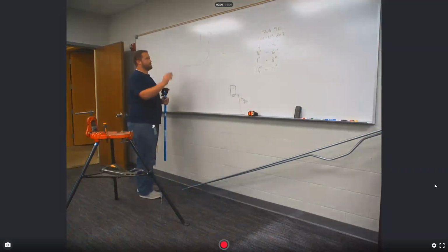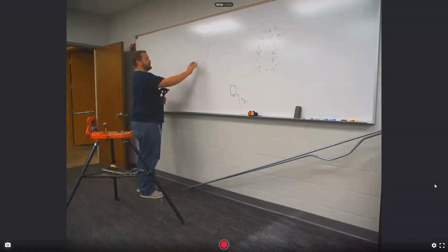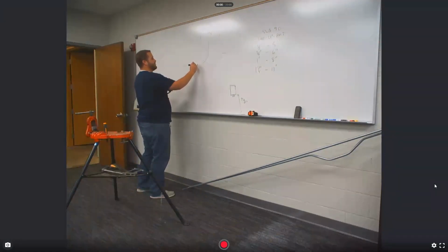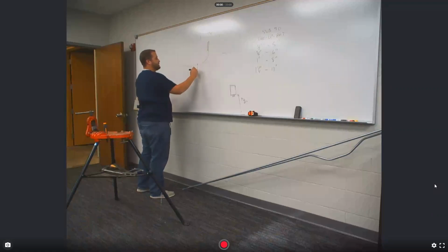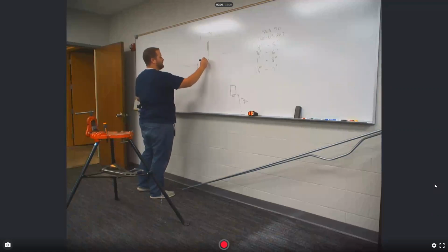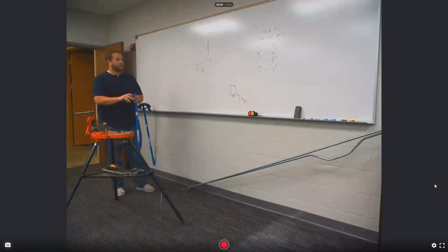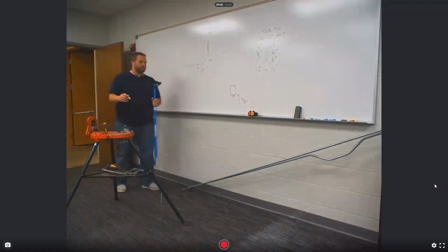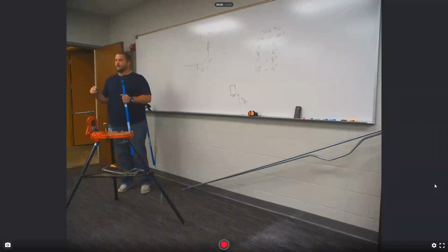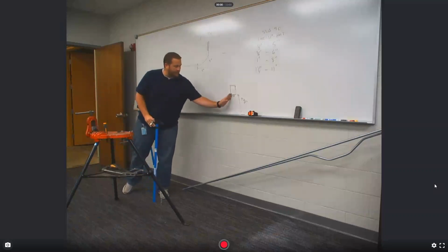So what that means is that the radius of this bend, what it takes up is, that's the start of the bend, and this is the start of the bend. This distance is, for 1/2 inch EMT, that'd be 5 inches. Make sense? So if I know that the radius of this thing is going to take up 5 inches, where would I need to start the bend of a 1/2 inch EMT pipe to get it to end up right at 9 3/8 inches?